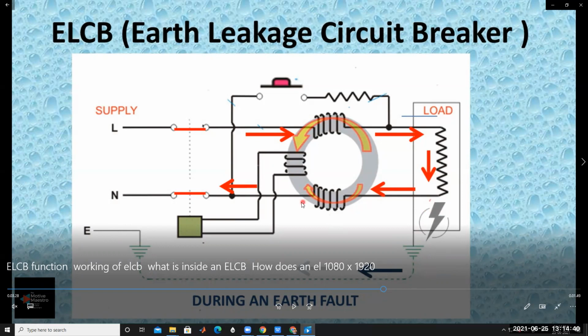In this case, the amount of current drawn from the supply is maximum. Some amount of current is leaving to the earth wire, and the remaining current is coming back through the neutral wire. Understood? For example, 5 amps coming from the line, and here 5 amps. This coil is energized by 5 amps, and the 5 amps is entering like this, and some amount of leakage current is passing through the earth wire.